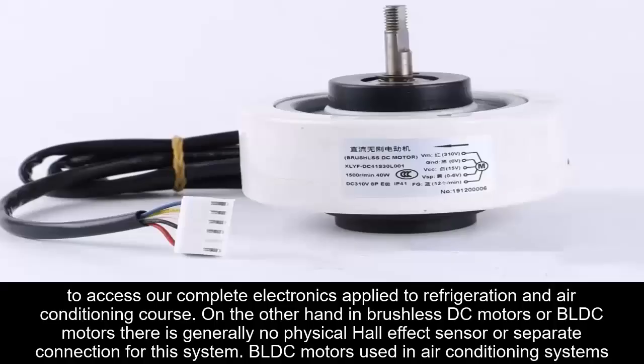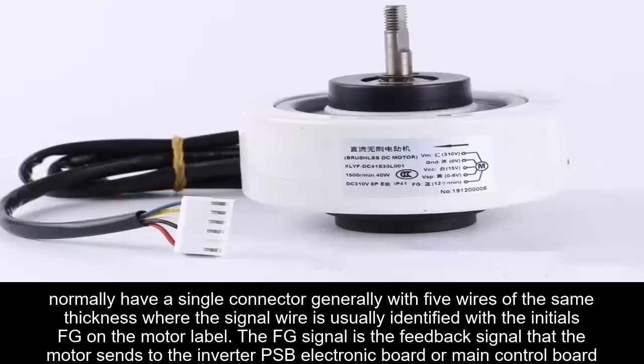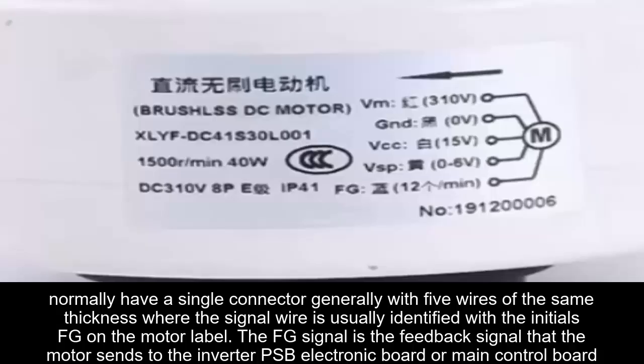On the other hand, in brushless DC motors, or BLDC motors, there is generally no physical Hall effect sensor or separate connection for this system. BLDC motors used in air conditioning systems normally have a single connector, generally with 5 wires of the same thickness, where the signal wire is usually identified with the initials FG on the motor label.